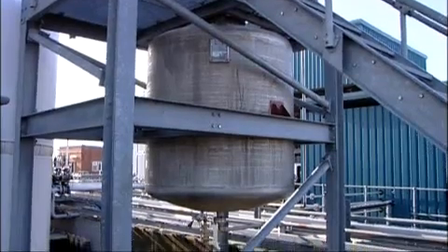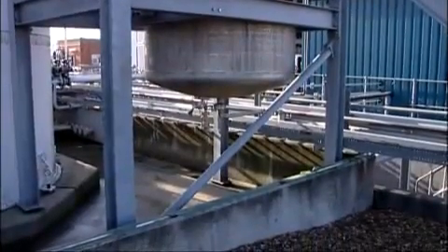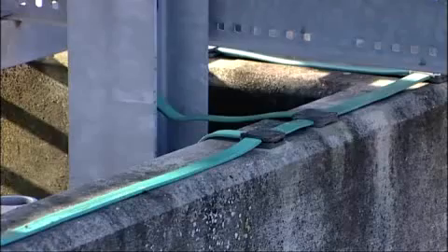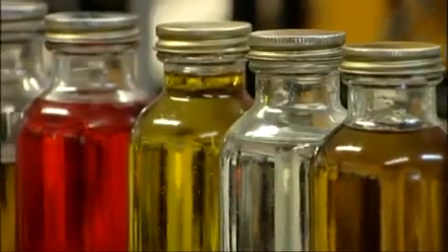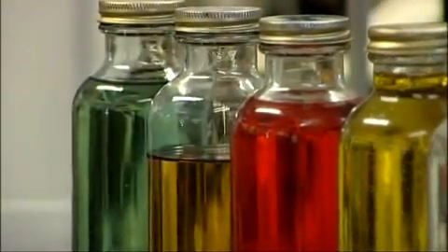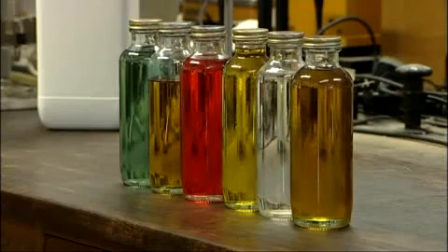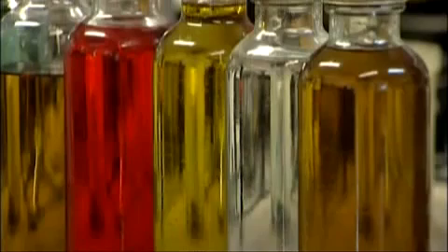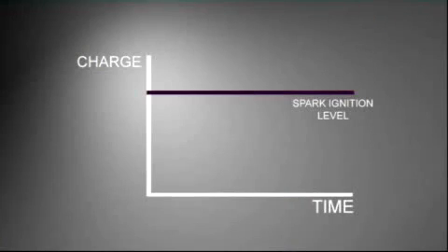The electrostatic charge built up in the liquid will dissipate by migrating from the liquid to an earthing point. The rate of dissipation depends on how readily the liquid will conduct electricity. Hydrocarbon solvents have low conductivities and do not readily conduct electricity. The slower the rate of charge generation, the more chance it has to dissipate and avoid reaching the level of charge sufficient to cause an igniting spark.